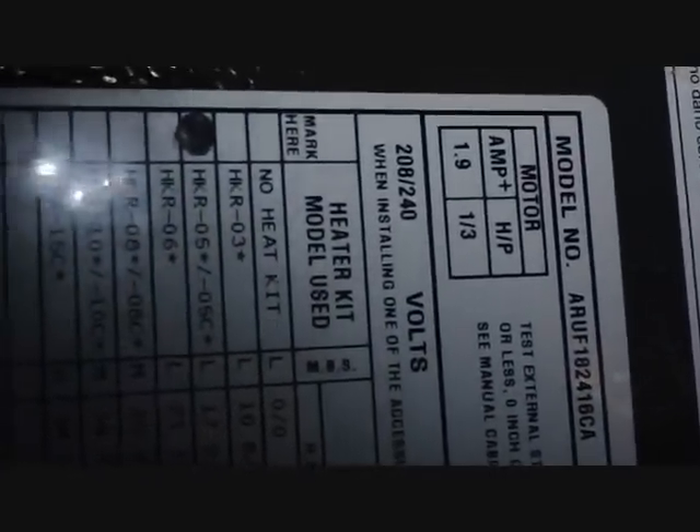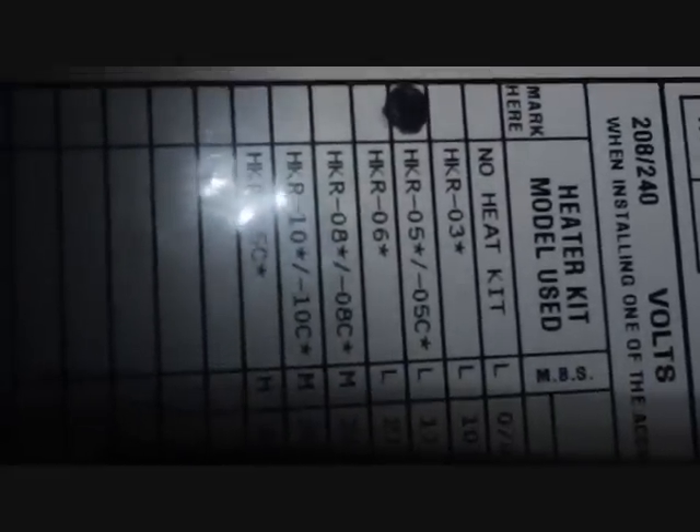This is our air handler — it's an ARUF 1824, basically Goodman's basic air handler that covers a ton-and-a-half to two-ton range. There's your third-horsepower blower. HKR-05 is just the five-kilowatt heat strip that's in the unit — it has to be marked for inspection and electrical purposes. There's your heating schematic for the heat strips, energy guide, and all 100% heat pump stickers. Goodman looks like the back of somebody's old car with the way they put all those stickers on the front.